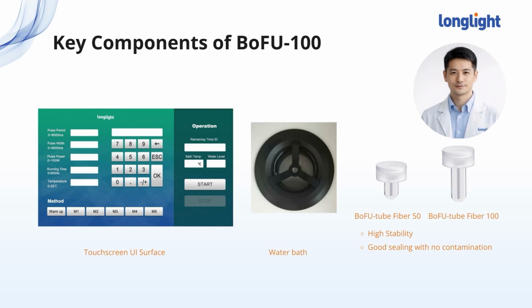BoFU 100 is the entry point into focused ultrasonication for many labs. It targets customers who mainly run one sample at a time, hospital labs, small oncology groups, or new NGS labs working with MGI instruments. Cooling is handled by an integrated water bath with semiconductor control from 4 to 25 degrees C, so temperature stays stable even during repeated runs. The dedicated BoFU tubes, Fiber 50 and Fiber 100, are leak-free and easy to handle, which reduces contamination risk and gives good reproducibility even for less experienced users. When you position the product, you can think of BoFU 100 as Covaris-class performance in a single sample box that fits easily into a clinician's lab or a small research group.